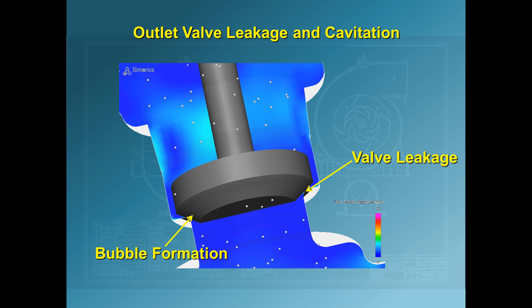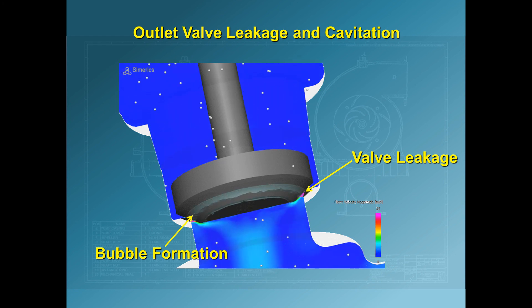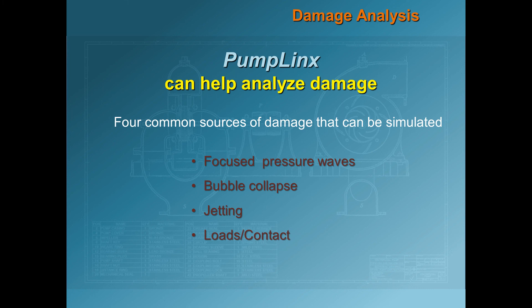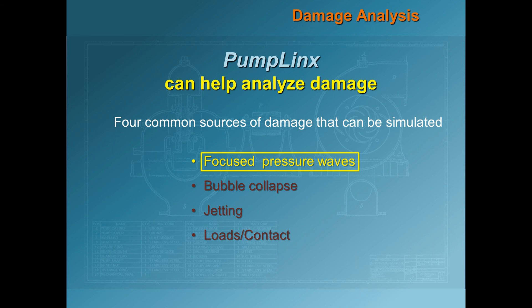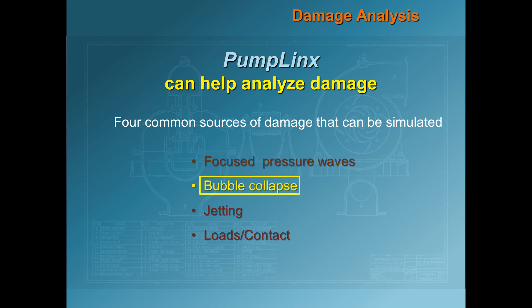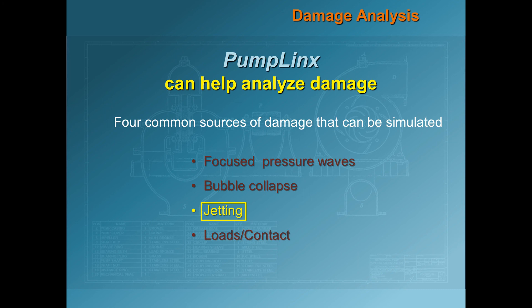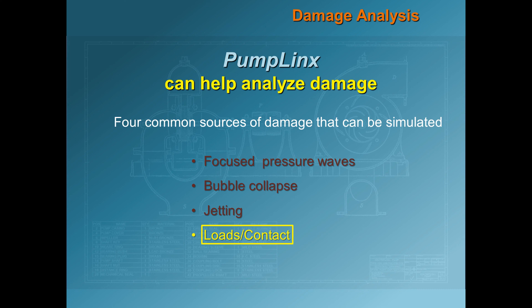This type of behavior often leads to hardware damage. Here are some common sources of damage which can occur in devices with valves and other systems with high pressure gradients. Earlier, we saw that pressure waves were created when the valves opened or closed. Also, jetting occurred under the outlet valve which led to the formation and collapse of bubbles. Finally, we saw that the outlet valve did not close completely, which caused leakage and jetting. The incomplete closing of the outlet valve was modeled this way intentionally to show how real hardware effects could be taken into account in a PumpLinx simulation. Another source of damage can occur when physical contact between components of the system occurs.